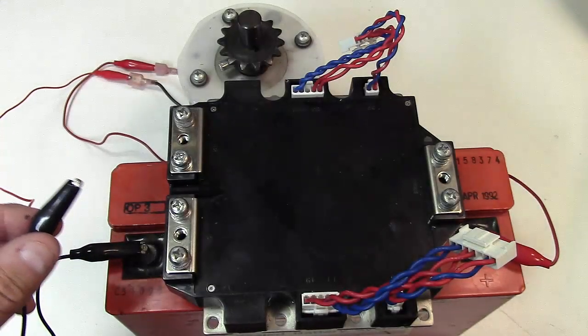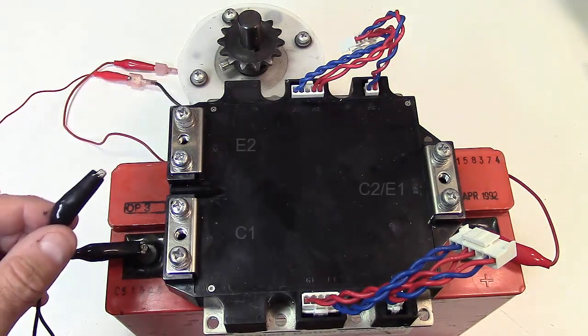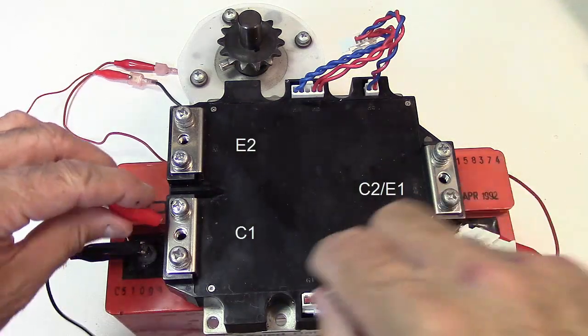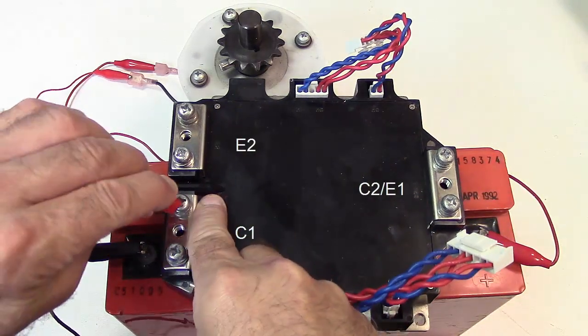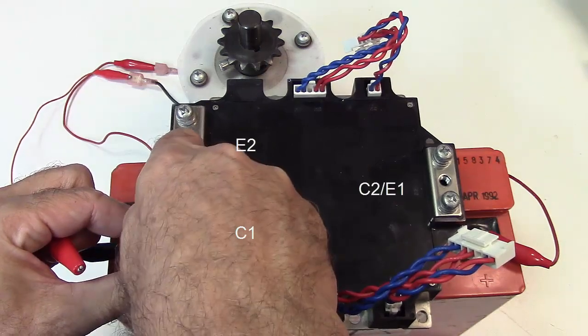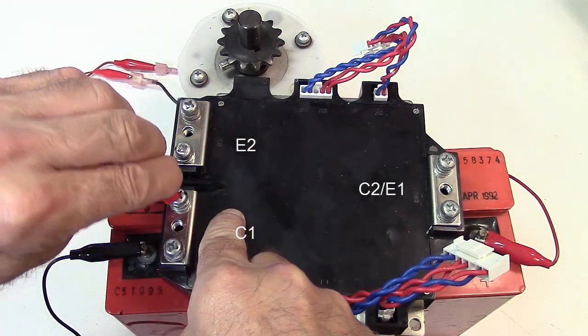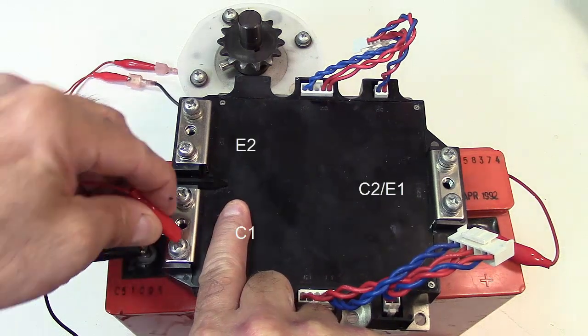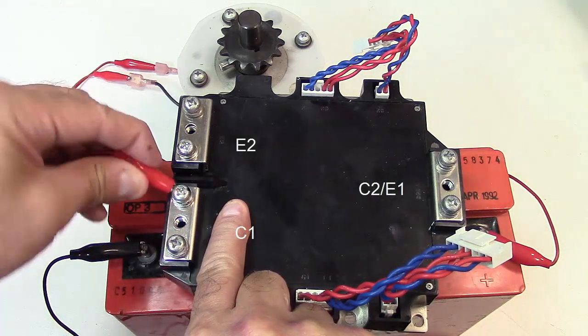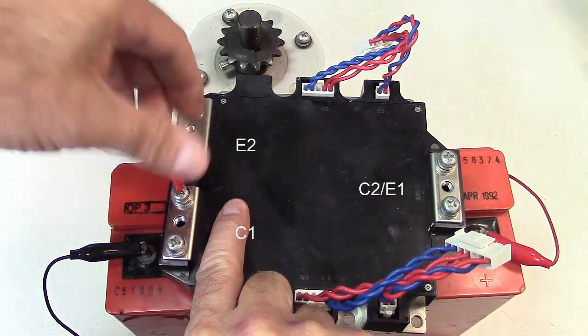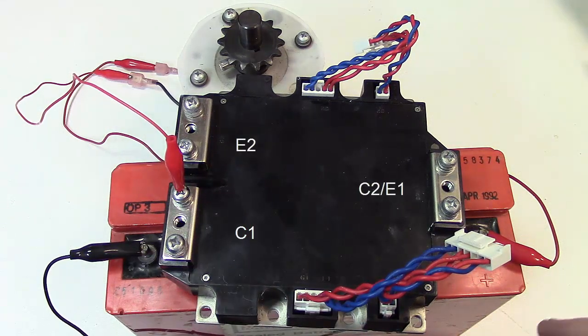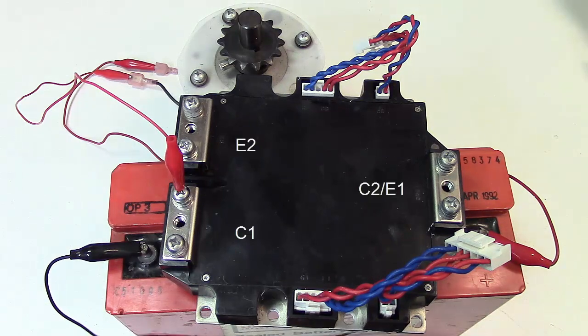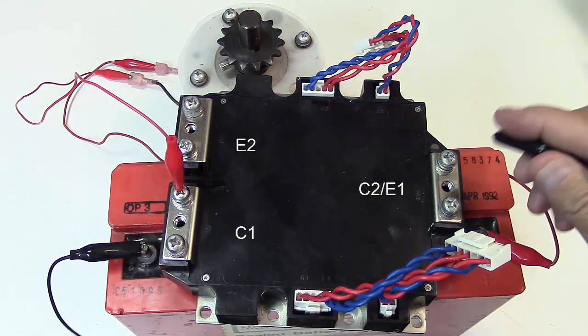Alright, on this particular module here, C1 is right here. So this is actually C1 and this screw is loose, I'm going to tighten that up. So this is C1, this is our collector of the top IGBT. So we're going to hook that up in series with our motor. And E1 is over here, on this side.